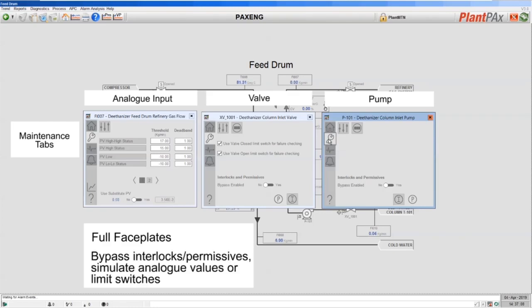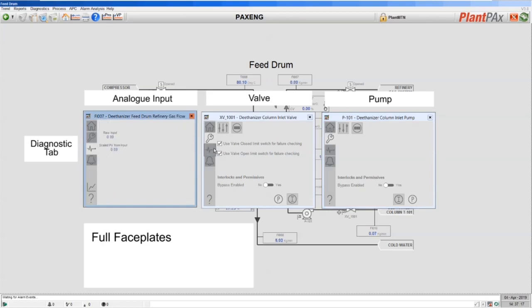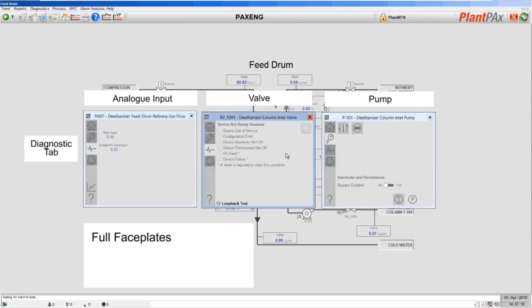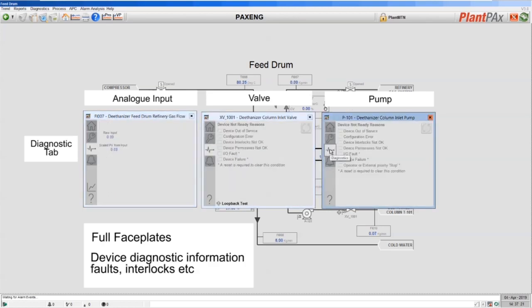On the maintenance tab I can also bypass permissives and enable simulation of analog values or input switches. On the diagnostics tab I will find the list of all the things that can prevent me from operating the device — so here for the valve I can see that I may not be able to open it because there's an interlock present or there's an I/O fault.